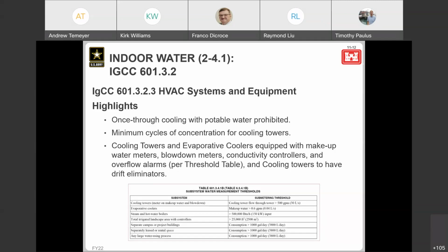And, real world, I've seen good and bad examples of this. I've seen several towers that are using a cycle of concentration of 1 or less. That means that they're going through a lot of water. That water usually has chemicals in there to help prevent scale and growth and things like that. So you end up seeing some of these things where things aren't tuned real well, and they're going through a lot of water and a lot of chemicals, and it's just all around not a good operation, and it gets pretty expensive.